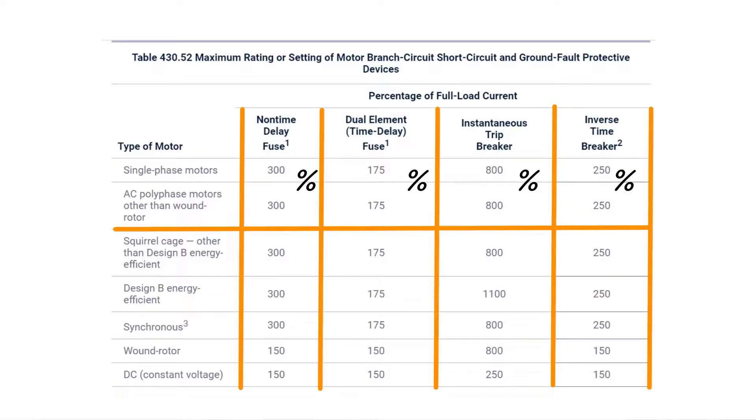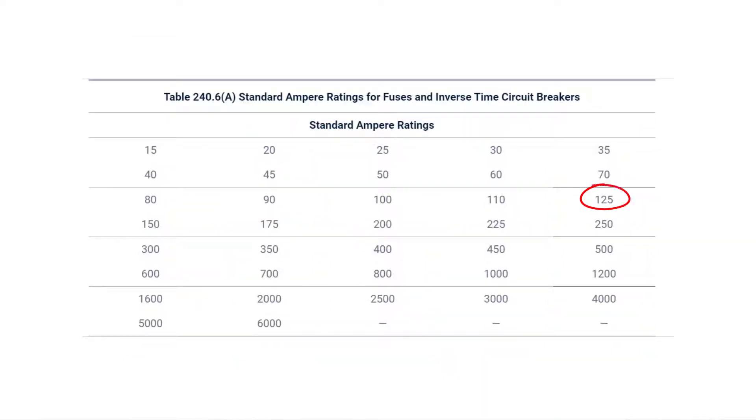That 240-volt fed single-phase 10-horsepower motor was 50 amps, right? If we were to use an inverse time circuit breaker, what's our percentage? 250. So 250% times 50 amps equals what? 125 amps. Is 125 amps a standard fuse or circuit breaker size? We can double check, we know, but we can cross-check.